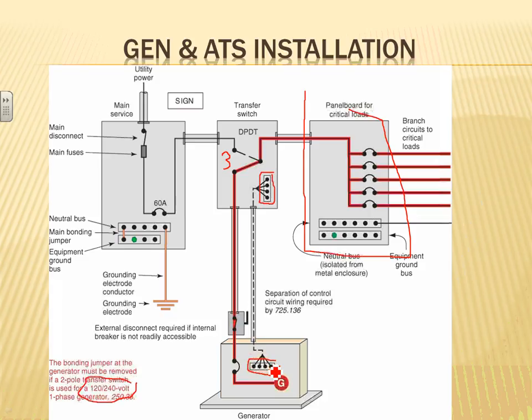So there's open transition, closed transition, and soft start. Soft start and paralleling go to the next level. But with closed transition, my understanding is you still have to have a relaying system, but because you're closing only momentarily and breaking, unlike soft start where you close forever and pick up load from this to this, it's cheaper, but still a lot more expensive than open transition.